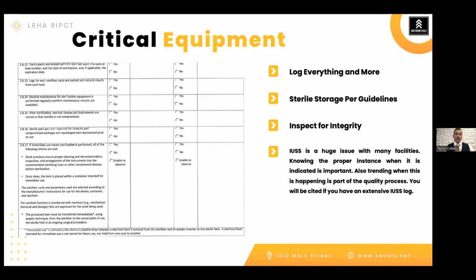Understand your requirements for sterile storage. Those items need to be stored in a separate area, possibly in a clean core or an area that's dedicated for sterile storage. And there are ventilation and temperature requirements for that area. So if you have that, that is an important piece that you want to make sure that they are done properly. The biggest thing that we see with sterile storage is compromised packets, or if there's expiration dates that a facility so chooses to use, expired things that just get pushed to the back. So that storage is extremely important, having all those items needed.